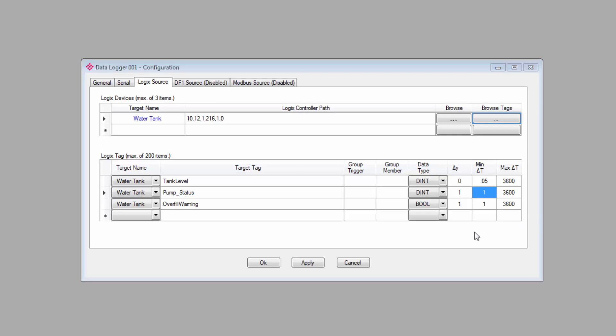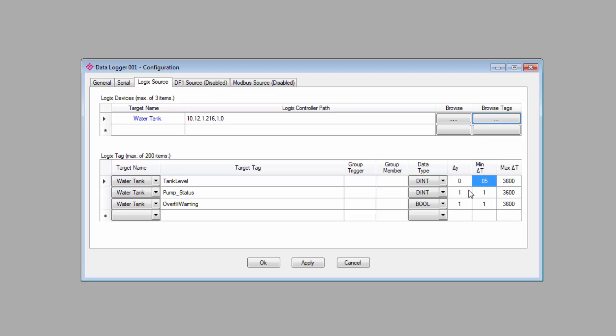Keep in mind that while our capacity of 16.777 million tags sounds like plenty of room, it can fill up pretty fast if you have a lot of tags that you're logging frequently. We can log data from up to 200 tags simultaneously, and if we logged all of those tags just once every second, you would completely fill up the database in less than a day. So, it's good to be a little conservative when setting the value change and minimum time interval.